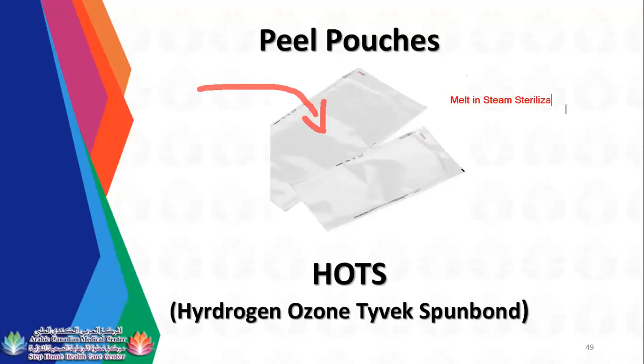The purpose of the plastic side, even for the other pouches, is to aid the visualization of the instruments by the user and the chemical indicator. That's why it is plastic. The paper side is where the steam enters and is removed. But for the Tyvek spunbond pouch, this plastic will melt in steam sterilization, so it should not be used in steam sterilization.